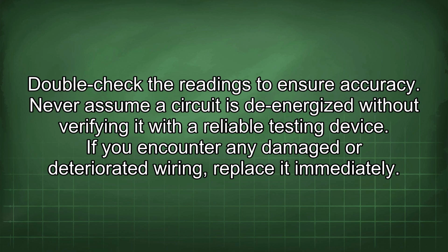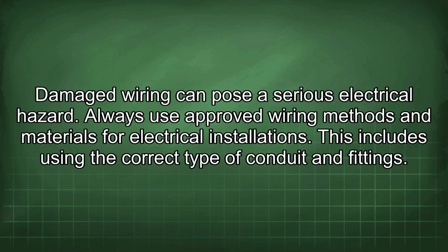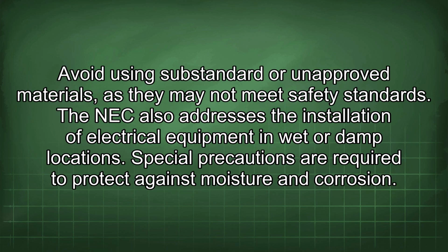If you encounter any damaged or deteriorated wiring, replace it immediately. Damaged wiring can pose a serious electrical hazard. Always use approved wiring methods and materials for electrical installations. This includes using the correct type of conduit and fittings. Avoid using substandard or unapproved materials, as they may not meet safety standards.